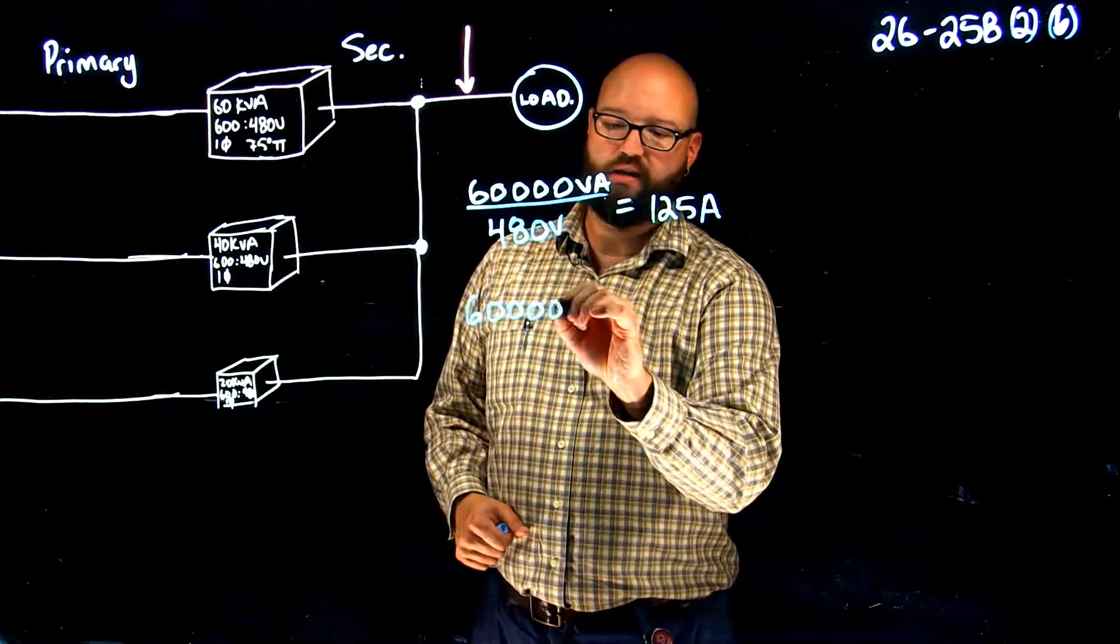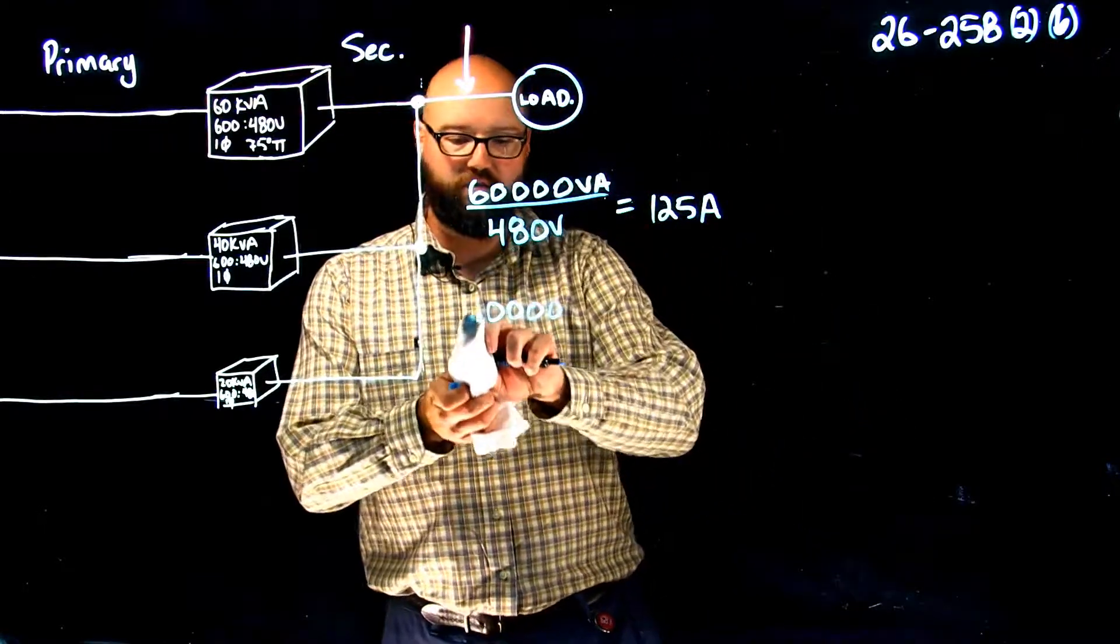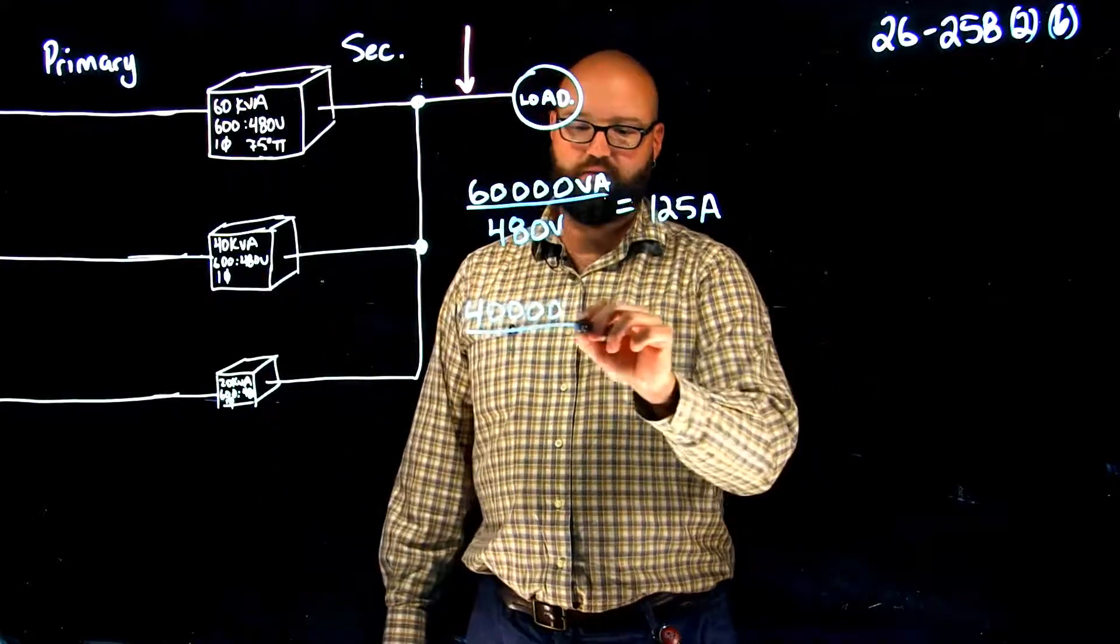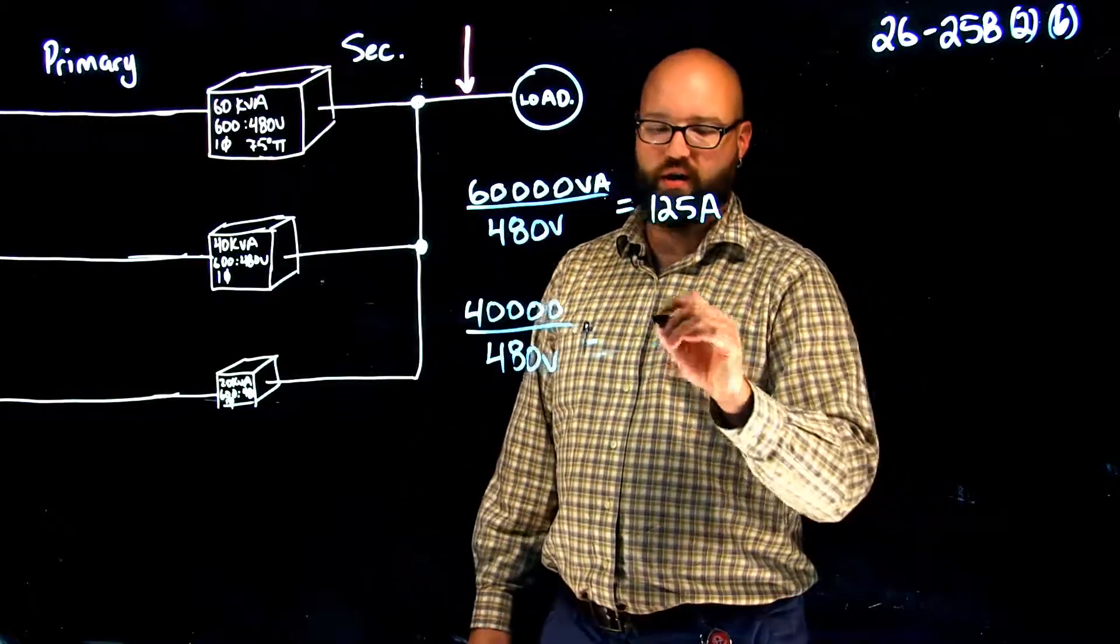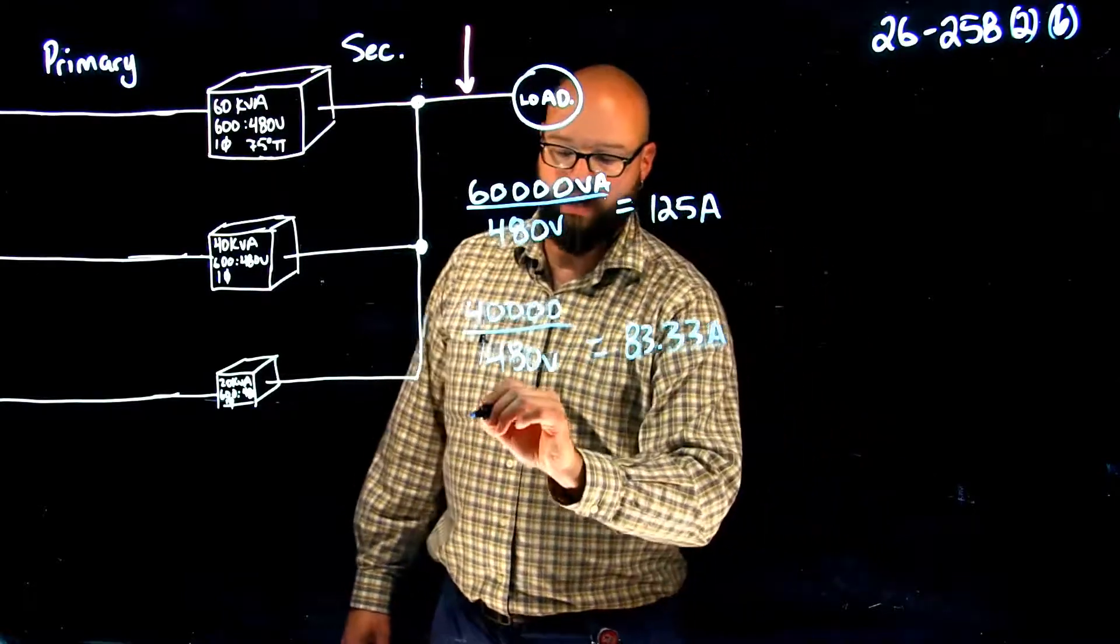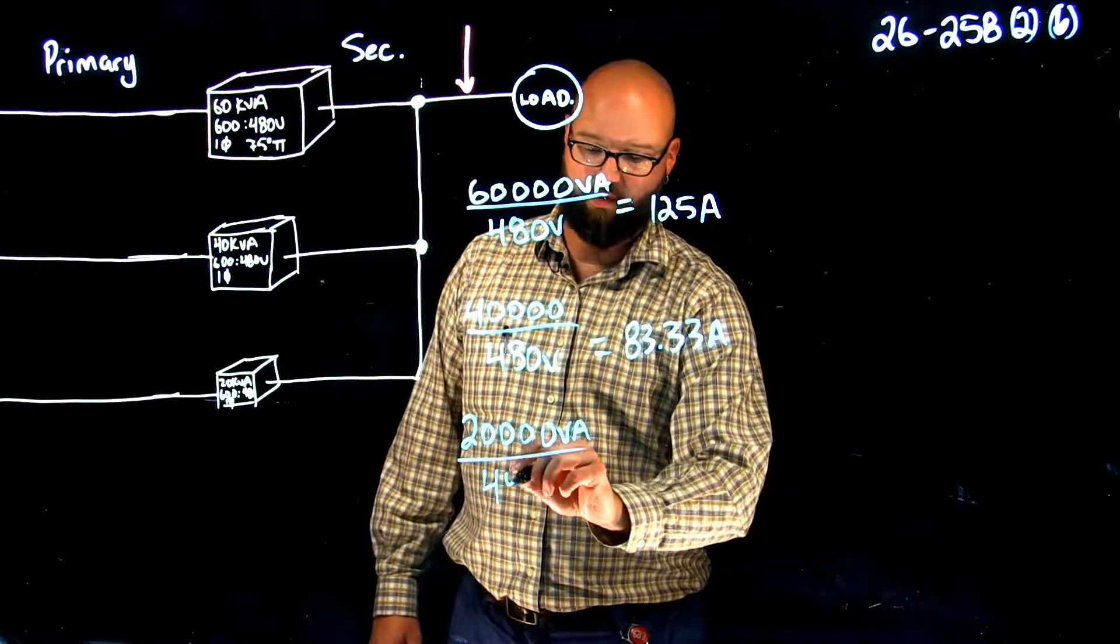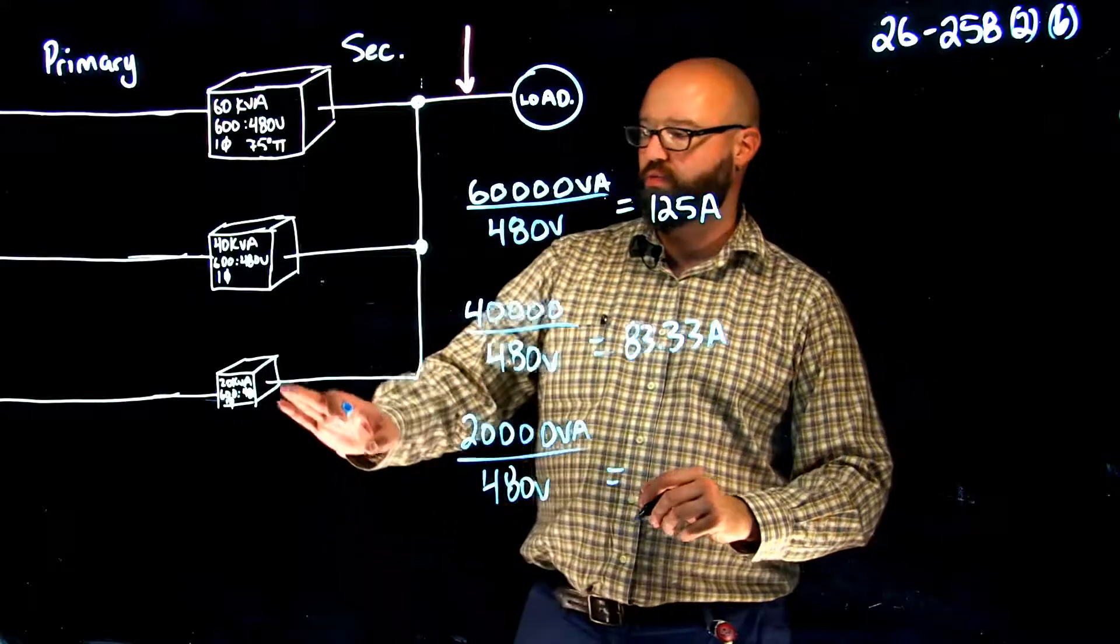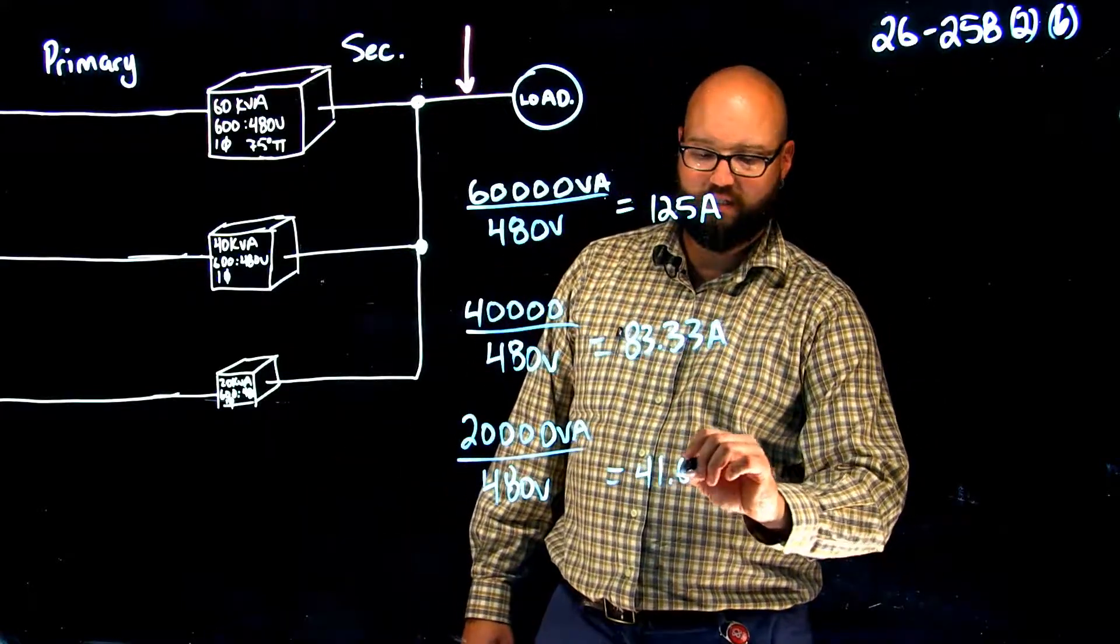We're going to look at our second, now we're dealing with our 40,000 VA transformer divided by our 480 volts gives us a secondary rated current of 83.33 amps, and our 20 kVA divided by 480 volts gives us a current rating on this 20 kVA transformer of 41.67 amps.